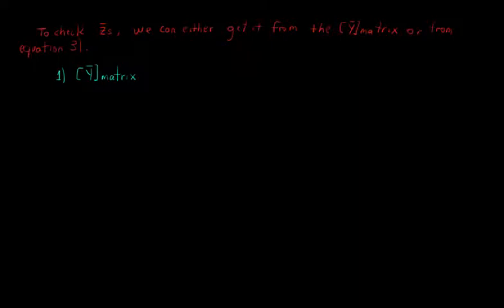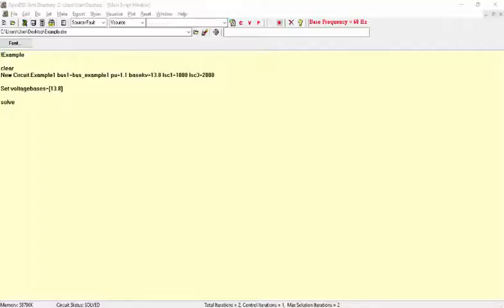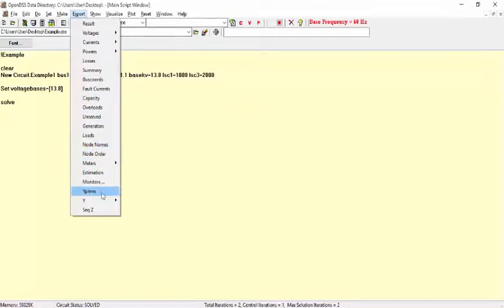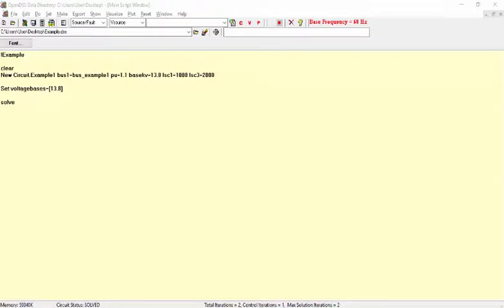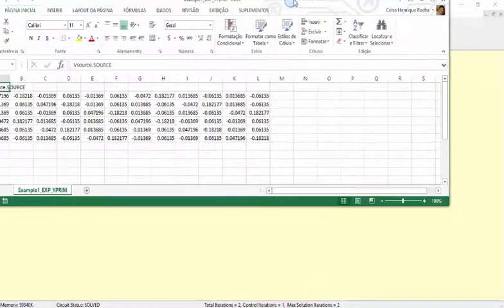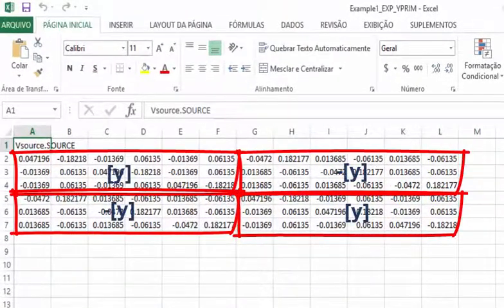The first one is to take it directly from the Y prime matrix of the vSource element, which is a 6x6 matrix with the following format, where the matrix Z 3x3 is the inverse of the small y matrix. To get this matrix from OpenDSS, after solving the circuit, go to export and Y prime. Notice that the matrix shown has 12 columns. It happens because the real and imaginary parts of the elements are in different cells. So if we want to get ZS from this matrix, we must take the inverse of one of these 3x3 sub-matrices.